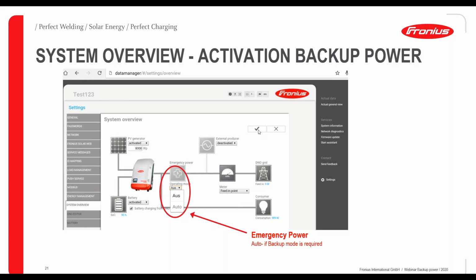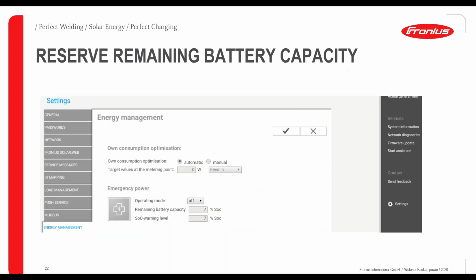So basically here on that page you can also adjust the battery, so you can activate the battery, choose the right battery, activate the PV generator, select the right PV power, and activate probably an external producer, maybe a second existing inverter, on-grid inverter, which has to be also activated here. And last but not least, the Fronius smart meter on the feed-in point also needs to be selected here. That's actually all about the settings. When you've done this, the inverter should run and operate.